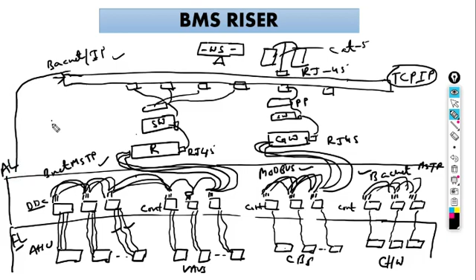Now let us understand one thing here. These devices, AHUs, VAVs, circuit breakers, chilled water system, and we have sensors here, right? So sensors from these devices to the DDC controller, this layer is called the field level. Okay, because these devices are inside the field, inside the systems, inside the equipments, right, in the field. From DDC to these connections, this is called the automation level. These DDCs, these controllers, this level is called the automation level, and from this automation level to this workstation, this is called the management level.